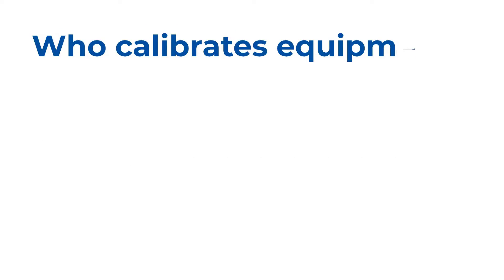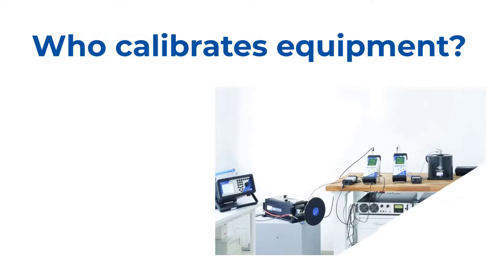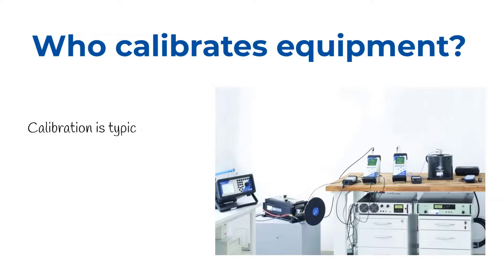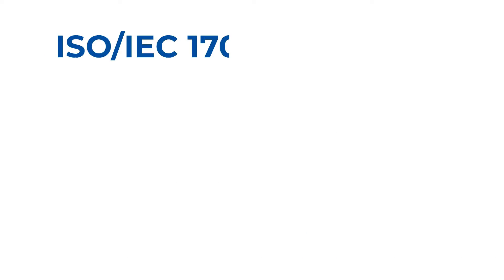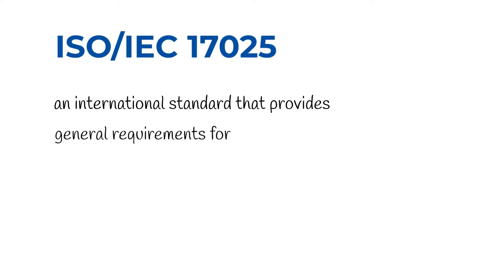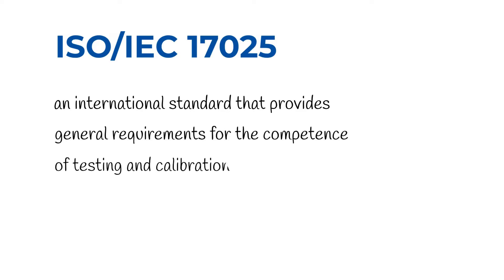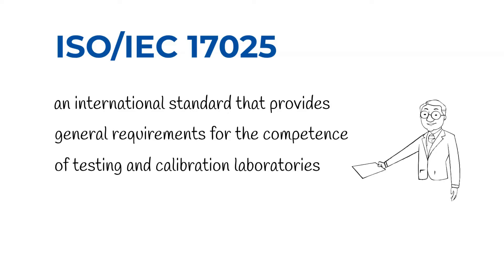To ensure that the instrument is reliable, calibration is typically done in a laboratory where conditions are controlled. The calibration will stay accurate under the same conditions it was calibrated in. The ISO IEC 17025 is an international standard that provides general requirements for the competence of testing and calibration laboratories.